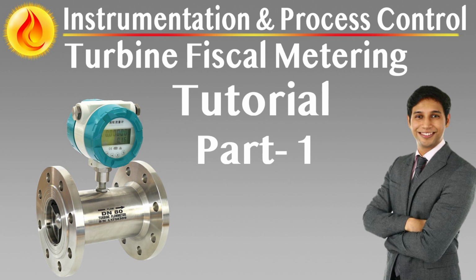Sample stream extraction and analyzer integration. A dedicated sampling line must be included to serve analyzer systems, such as online densitometers, water cut analyzers, or composite samplers. The extraction point is typically located upstream of the meter runs and prover loop to reflect the fluid condition prior to any metering bias or mechanical interaction. If required by the process or installation constraints, the sampling point may alternatively be located downstream, provided it remains representative and justified in the sampling protocol.